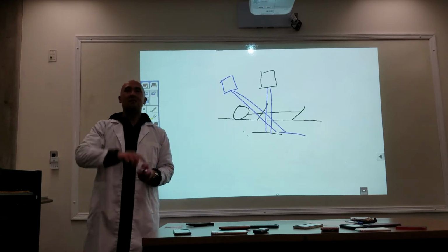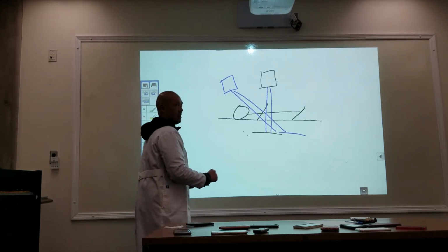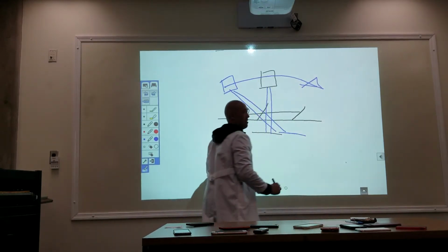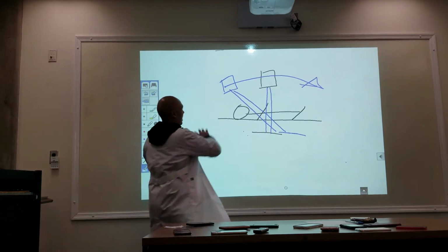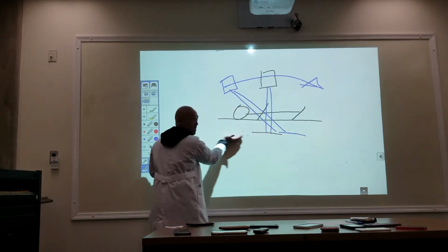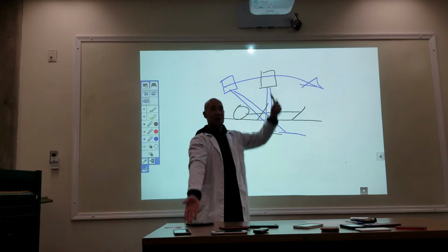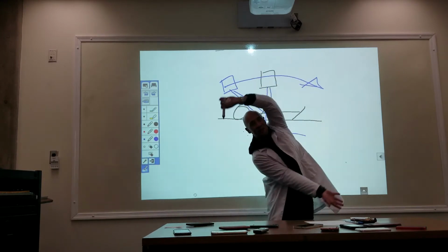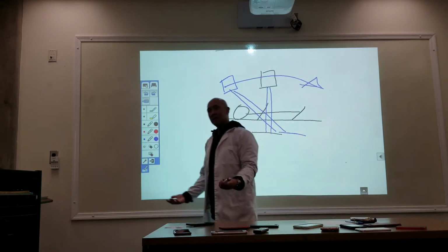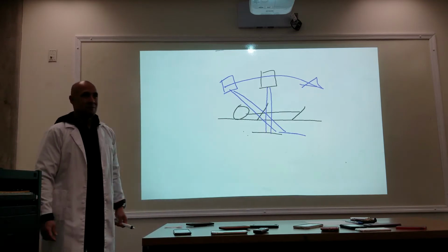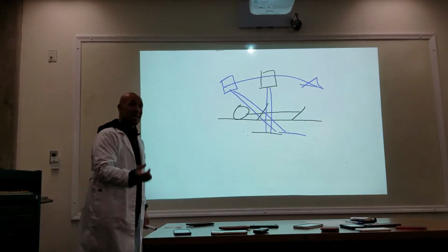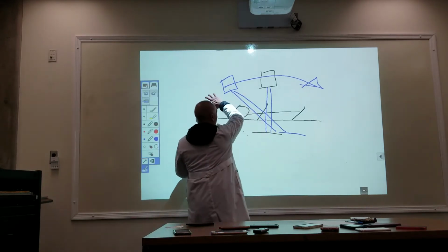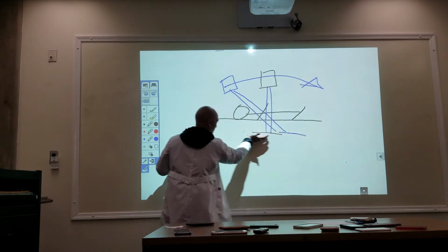When we make an exposure, this tube is going to swing from top to bottom. And as that tube's moving, so is the Bucky. So it's moving like this. Okay? What is the objective of that? We're literally taking an X-ray in motion. We're taking an X-ray in motion because as it's making exposure, it's going beep.